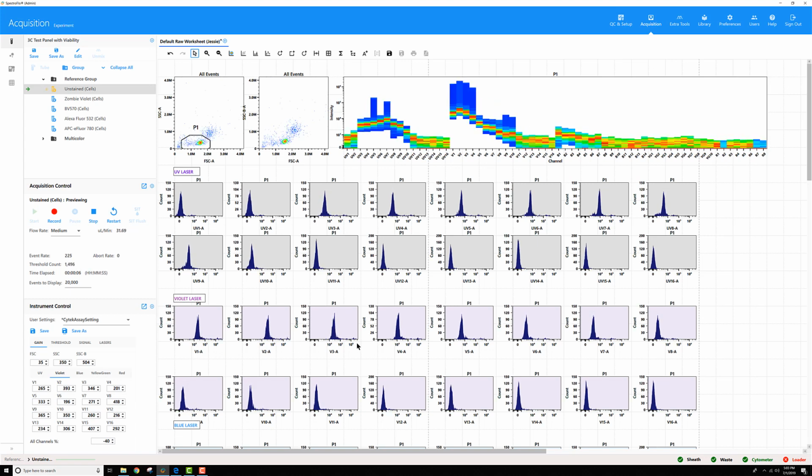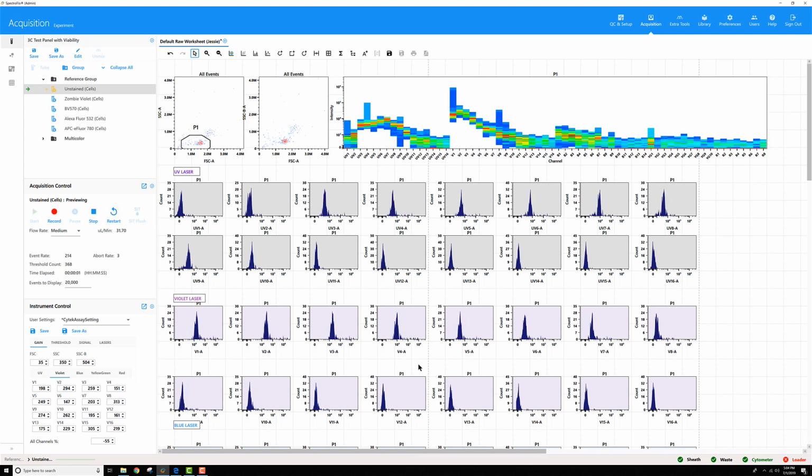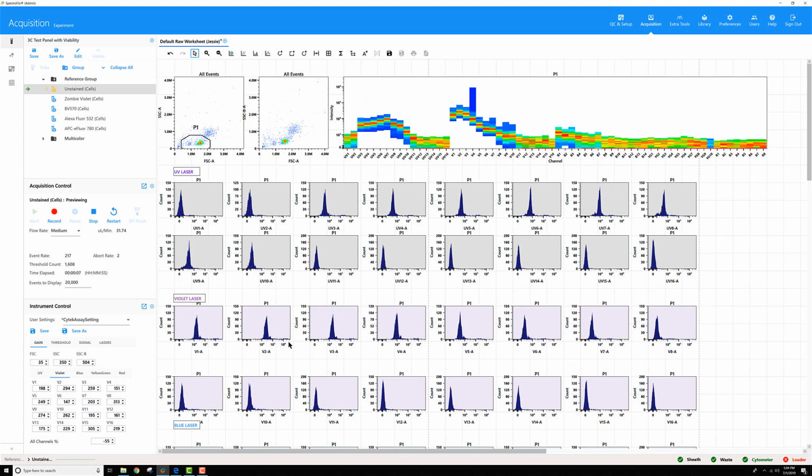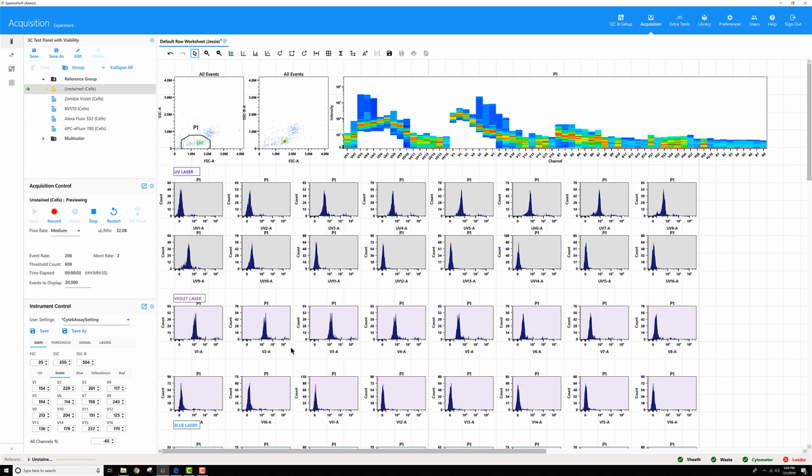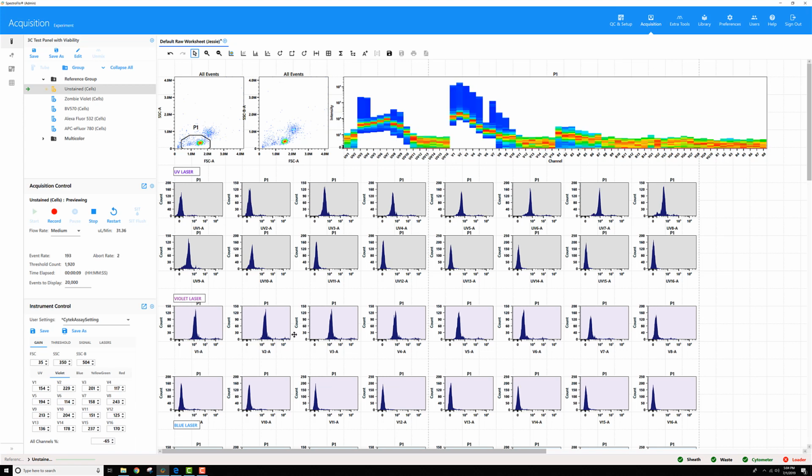Okay, looks like V3 and V2 might still be a little high, V1 as well, so let's see what minus 55% looks like. Still might need a little bit more. I'm seeing a few events crop up on these high bright violets. Let's do minus 65%. Okay, this should be close. I might still need to go a little bit further.